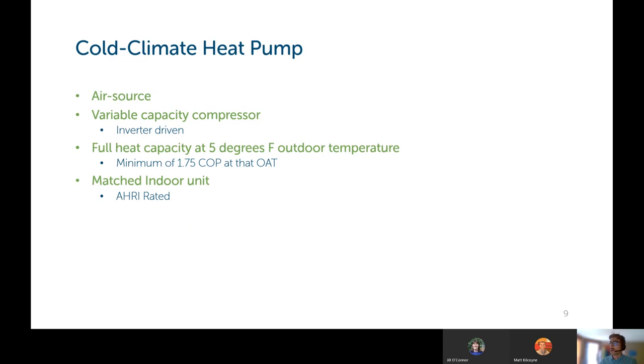Another useful definition for this presentation is a cold climate heat pump. They are air sourced. They have a variable capacity, inverter driven compressor. They must be able to heat at full capacity down to 5 degrees outdoor air temperature, and at that temperature have a minimum coefficient of performance of 1.75. And these cold climate heat pumps must be matched to an indoor unit that has been AHRI rated to the outdoor unit to prove that coefficient of performance at 5 degrees.